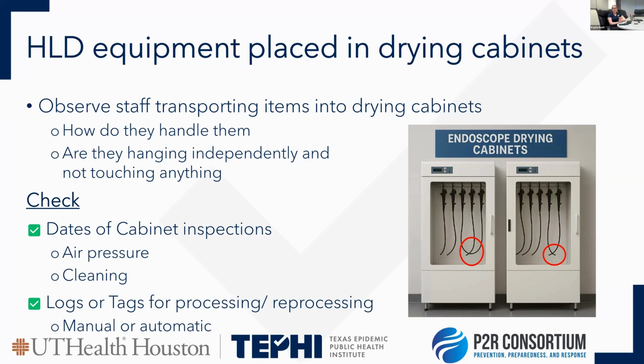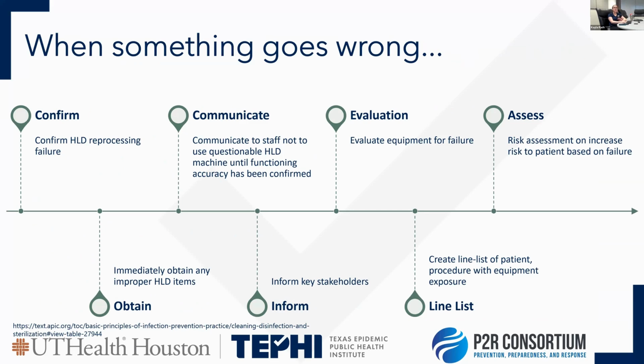So another thing that comes in with scope processing is that AAMI and OSHA really recommend reprocessing scopes in 7 days if they have not been used. So if you have a scope hanging and it has not been used in 7 days, it needs to be reprocessed, which means it needs to be rerun through high-level disinfection and then hung up. So you should also have logs or tags to indicate the last date of reprocessing for that specific scope and the date of the next reprocessing. So that tag should say when it was processed and when it needs to be reprocessed. And then how do you log and track that within that device too. So make sure that from start to finish, you know your process, you know the steps, and then you're monitoring them, because that will come into great effect and ease when something does go wrong.